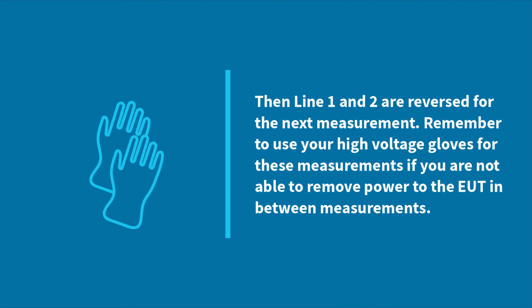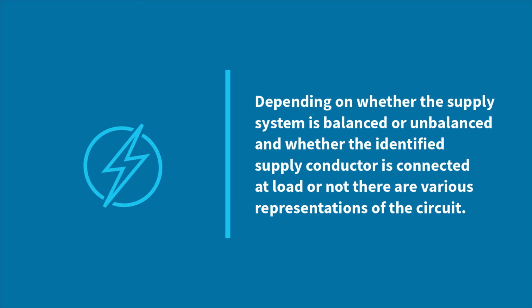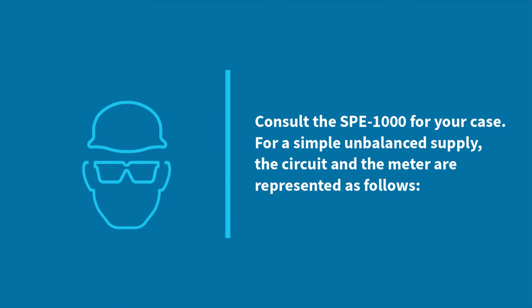Turn off the power. Then line 1 and 2 are reversed for the next measurement. Remember to use your high voltage gloves for these measurements if you are not able to remove power to the EUT in between measurements. Depending on whether the supply system is balanced or unbalanced and whether the identified supply conductor is connected at load or not, there are various representations of the circuit. Consult the SPE 1000 for your case. For a simple unbalanced supply, the circuit and the meter are represented as follows.